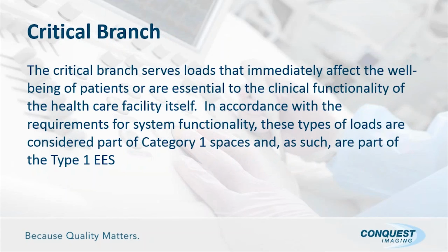When you talk about the critical branch, it serves loads that immediately affect the well-being of patients or are essential to the clinical functionality of the healthcare facility itself. In accordance with the requirements for system functionality, these types of loads are considered part of Category 1 spaces and as such are part of the Type 1 EES. Again, we've defined these devices as a Category 1 risk factor, and as such we have to use the Type 1 EES in support of them.